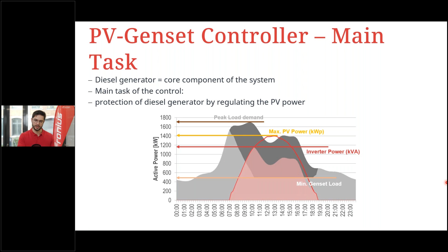As we've seen, the main tasks of the PV-Genset controller are to protect the diesel generators by regulating the power. Because there's a PV-Genset minimum load we don't want to fall below, inverter power needs to be cut down and curtailed at some point. So basically, we're talking about protection, a security component in the system, managing peak load demand.